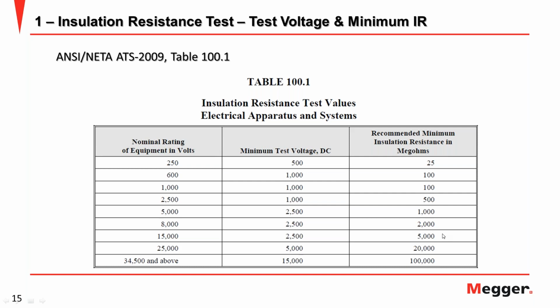This is if you only refer to this standard, but actually to analyze the insulation resistance, mostly the best way is trending analysis. You need to trend it time by time. If you see something change, maybe the insulation suddenly going down, even though it is still over the limit, you need to be careful because your insulation has already started to deteriorate.